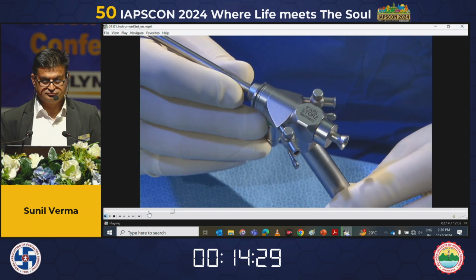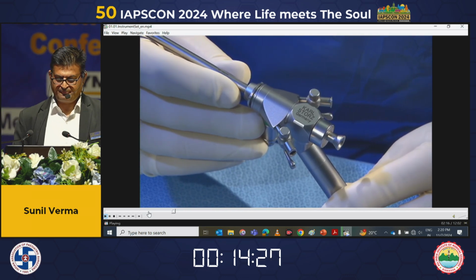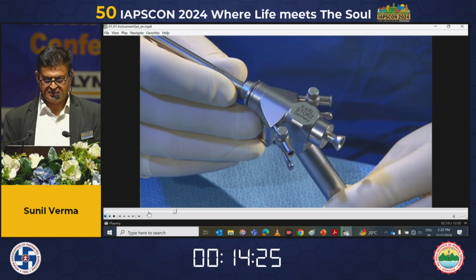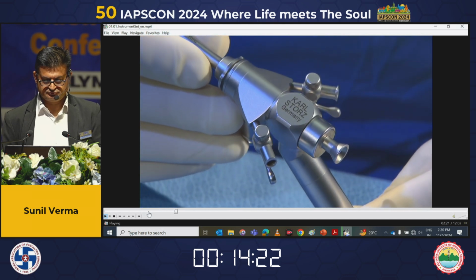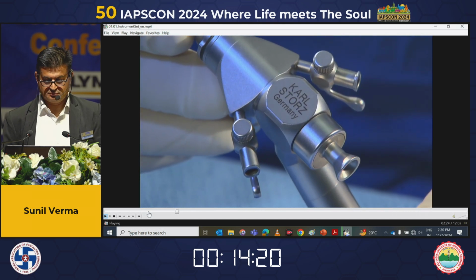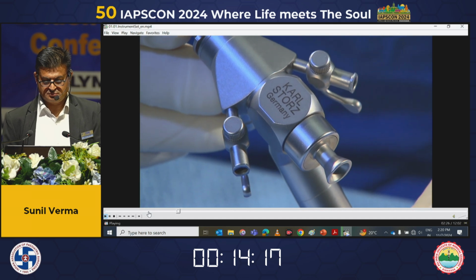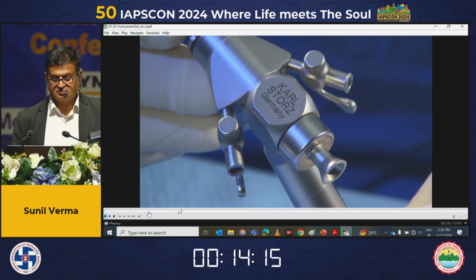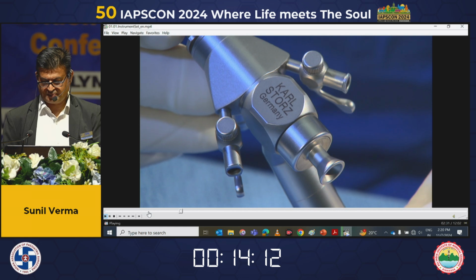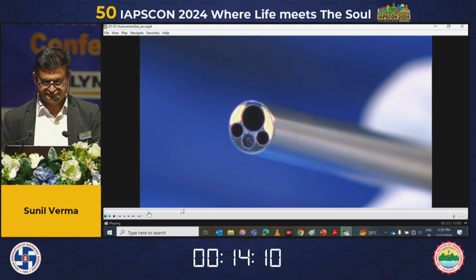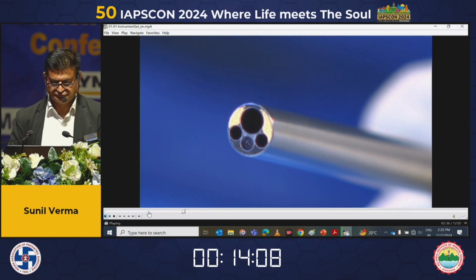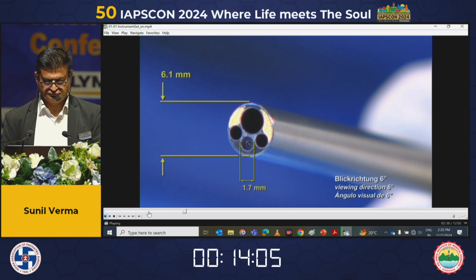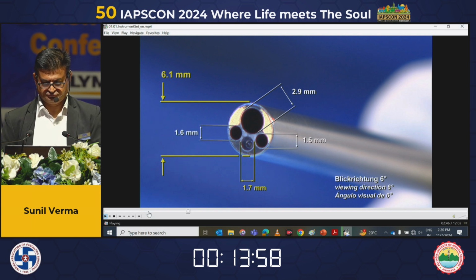The ventriculoscope has one large straight main working channel and two small side channels. The large working channel has a funnel-shaped entrance in order to facilitate the insertion of instruments. With the straight working channel, rigid instruments can be used which offer tactile feedback. The large working channel has a diameter of 2.9 mm. The two side channels have a diameter of 1.6 mm and can be used for irrigation or for a second instrument when working bimanually.